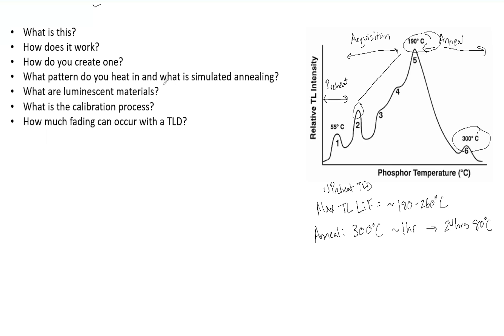Now what is the calibration process? I've already talked about annealing quite a bit, so you know you have to anneal this. The calibration is the thermoluminescent output versus the dose in the phosphor. This is linear up to 10 gray. Samples are irradiated to known doses to create a reference, and then when you heat one you don't know the irradiation rate, that will allow you by comparing to determine how much dose that has received.